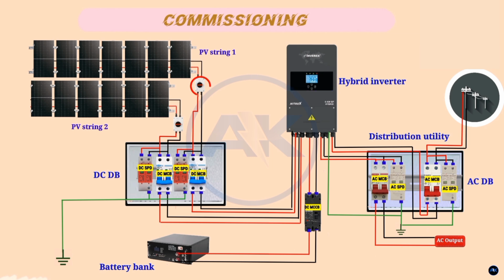The third thing to do is turn on the PV switch and PV isolator switch. If you did not use any external PV isolator switch, you only have to turn on the inverter switch. Next is to turn on the DC/MCB for PV input and then turn on the AC/MCB for inverter grid input. Wait a few seconds before doing anything else. When everything seems to be fine, the next thing to do is turn on the AC/MCB for inverter AC output, and now your solar power system is ready for service.